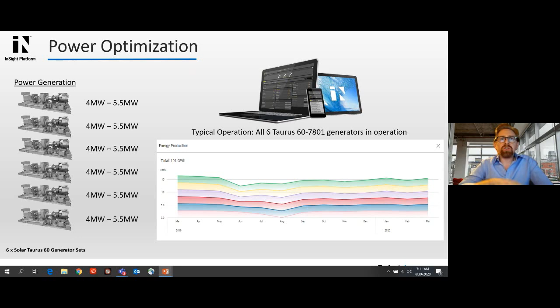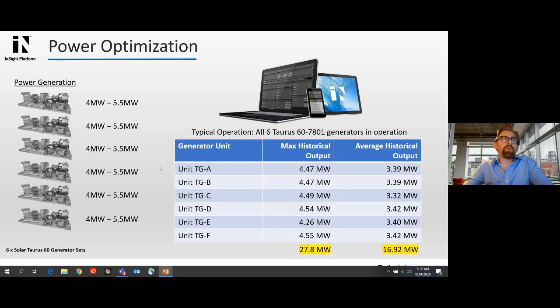When we actually look at the historical data, you'll see that units A through F, at their max, in the last year of operation, we never saw anything above 4.55 megawatts, whereas the average historical output was closer to about 3.3 or 3.4 megawatts.